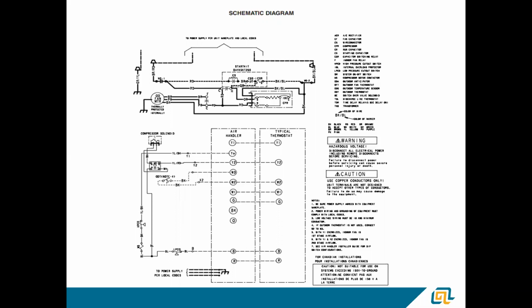Here's another schematic, basically the same thing. Here's our capacitor. Here's our compressor right here. Run, start, common windings. This is actually a two-step scroll wiring diagram. You can see right here they've got this little compressor solenoid. That's what loads and unloads the scroll compressor. One of the things I wanted to show you here is that the low pressure control in this is actually breaking the common wire. So you'd have no connection to common. It isn't in the Y circuit coming to the contactor. It's actually on its own in the common wire.